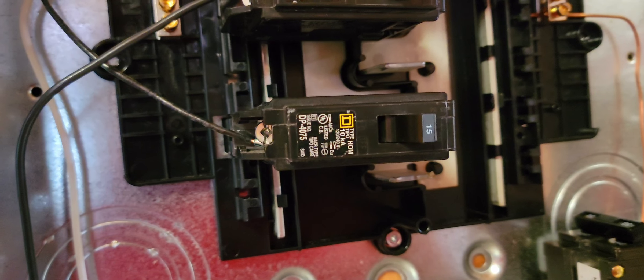That's my main panel. In the panel, I use a 30 amp as the main breaker coming from the inverter. On the right here, you see a 15 amp circuit, a 20 amp circuit, and also a 15 amp circuit. Those 15 amp circuits I use for lights, and the 20 amp circuit I use for the outlets so I can plug in more stuff.